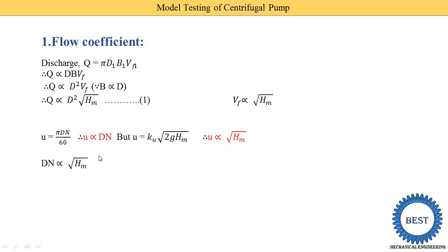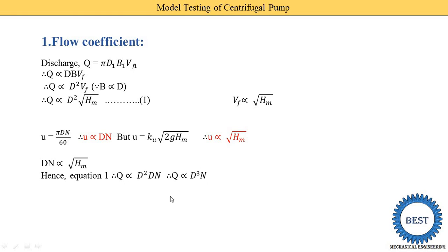Now we put this into equation number 1. The value of HM — where √HM is proportional to D·N — is substituted into equation number 1. So this √HM is replaced by D·N. What we get is: Q is proportional to D² × D·N, meaning D² × D·N = D³·N. So the equation is Q is proportional to D³ × N, meaning discharge is proportional to diameter cubed and the speed. Now removing the direct proportionality and adding a constant factor, D³·N goes to the left side, giving Q/(D³·N) = constant. This equation is called the flow coefficient.